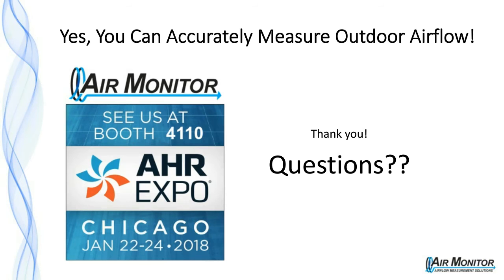Generally speaking, the louver free area, what that means in terms of design, is there's a velocity that's used, kind of a worst case velocity for carryover. For us, we want to compare the velocities to that face area so that we know what the CFM readings are across that range. We're not really interested in trying to figure out what the actual velocity is on either side of the static pressure device in terms of what our equations and metrics are.